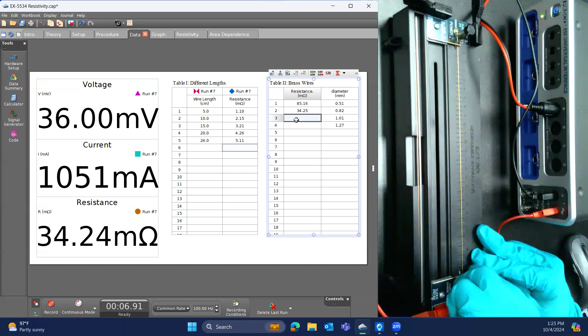Swap this out, make sure to park your sliding probes first and then loosen. You'll notice when you do it correctly, it doesn't pinch or bind when you loosen the screws while the probes are still in contact. That's why it is important. And the third one. I'm wearing gloves also, as you may be wondering, so I don't transfer any of my oils onto the sample pieces here, which can affect the conductivity on the surface.